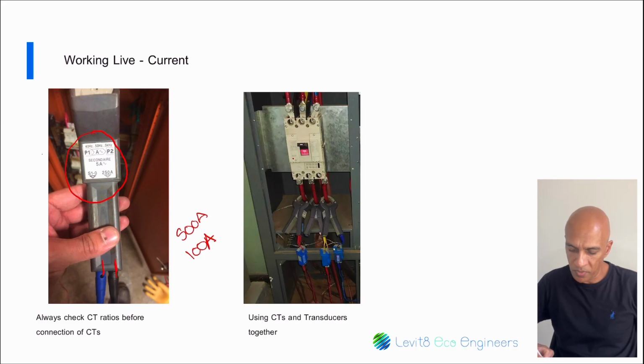So this bridge piece, there's a little bridge wire that goes between S1 and whatever ratio you want. So you could connect it, if you want a 250 ratio, between S1 and 250, and if you want a 500 ratio, you connect it between S1 and 500, and if you want 1,000, you connect it between S1 and 1,000. Now what happens here? The bottom has a bridge wire, as I mentioned previously, that connects the S1 to the correct amps. Now, have a look at this photo on the right.